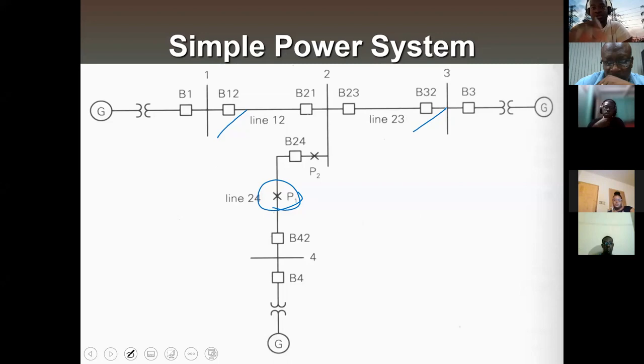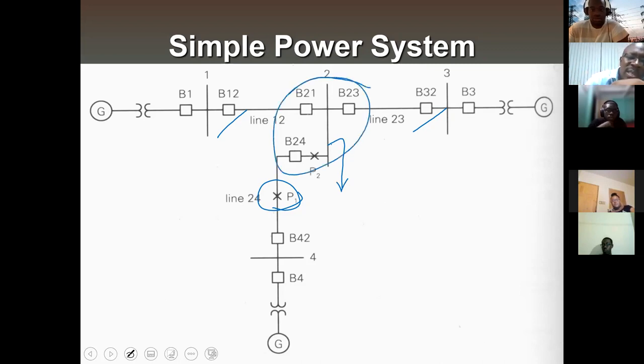What I was saying, if we're opening these, why would we still attempt to energize the rest of the line? It's not a matter of trying to energize the rest of the line. The point is, what you have is a bus fault. The protection system you set up for the bus would recognize the fault on the bus, having escalated, so it would take out the breakers associated with the bus bar.